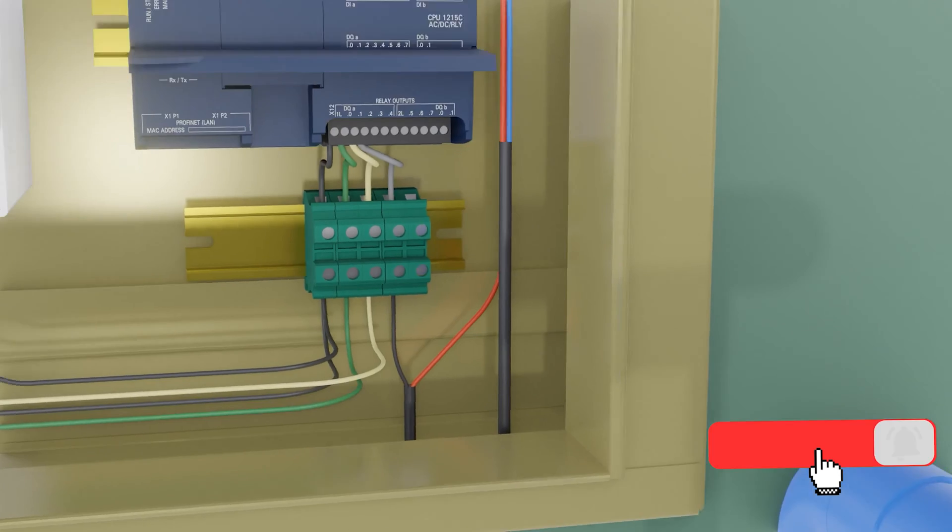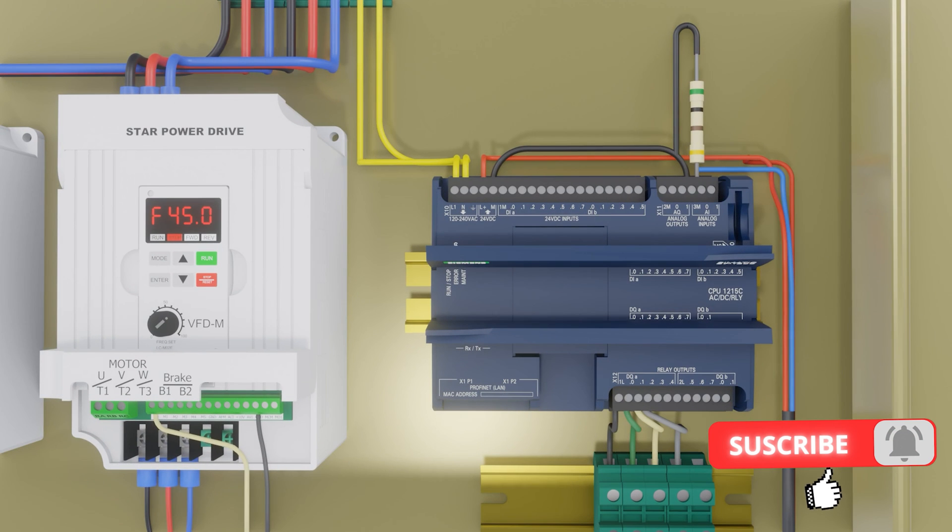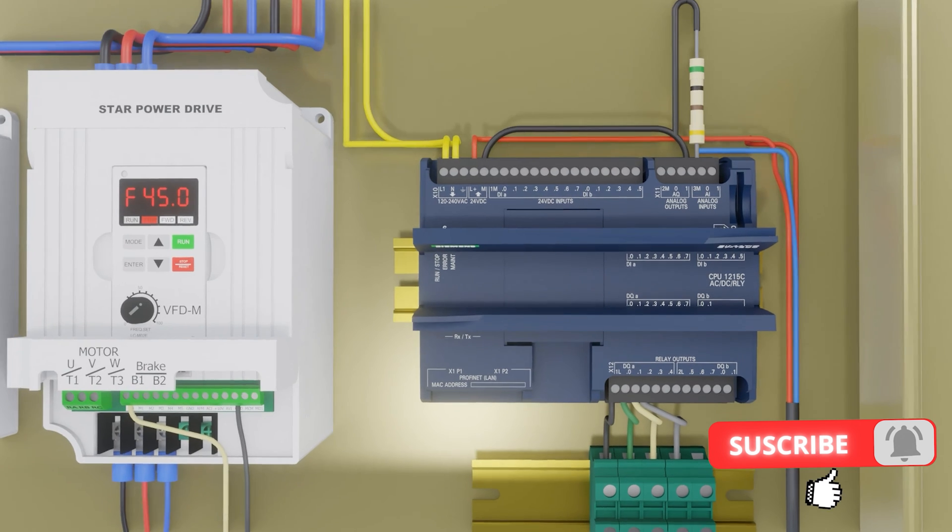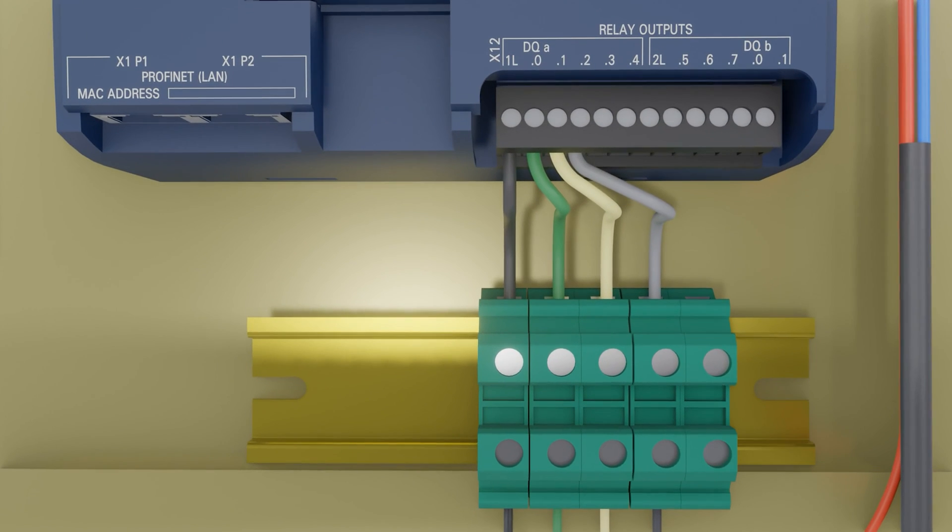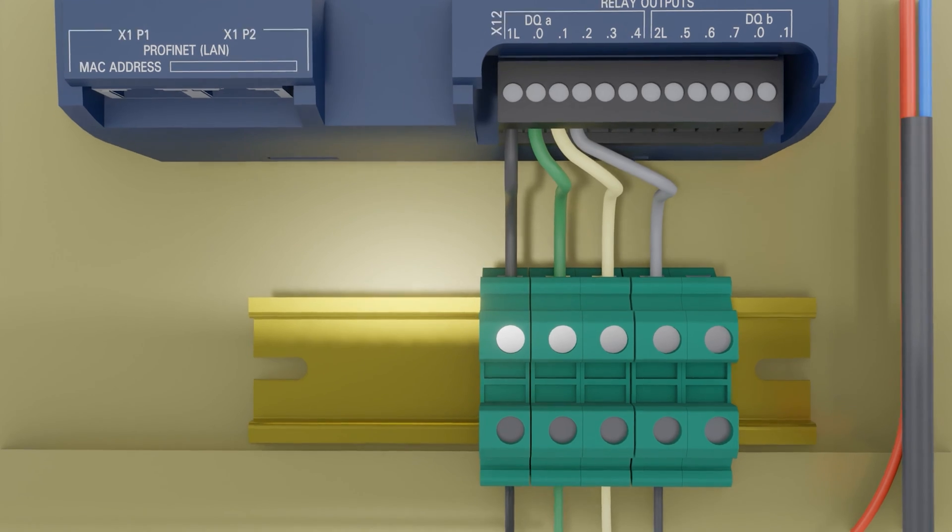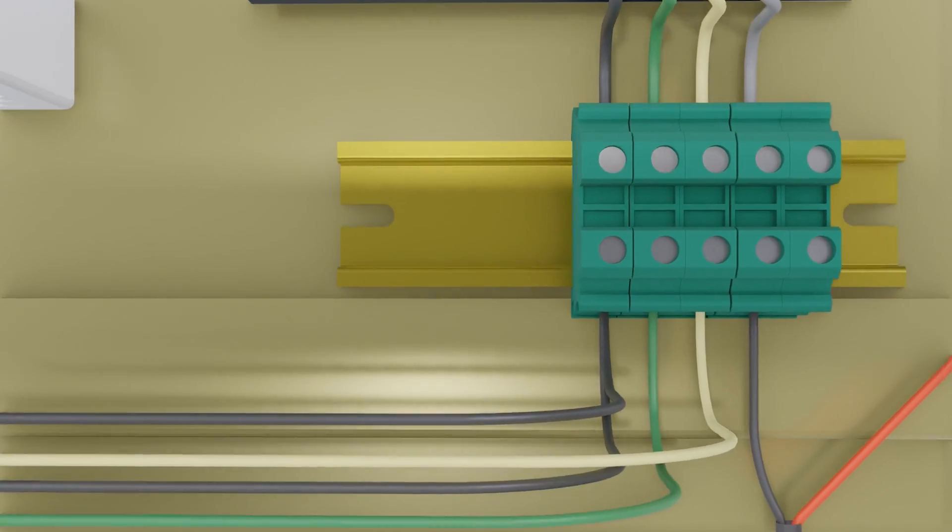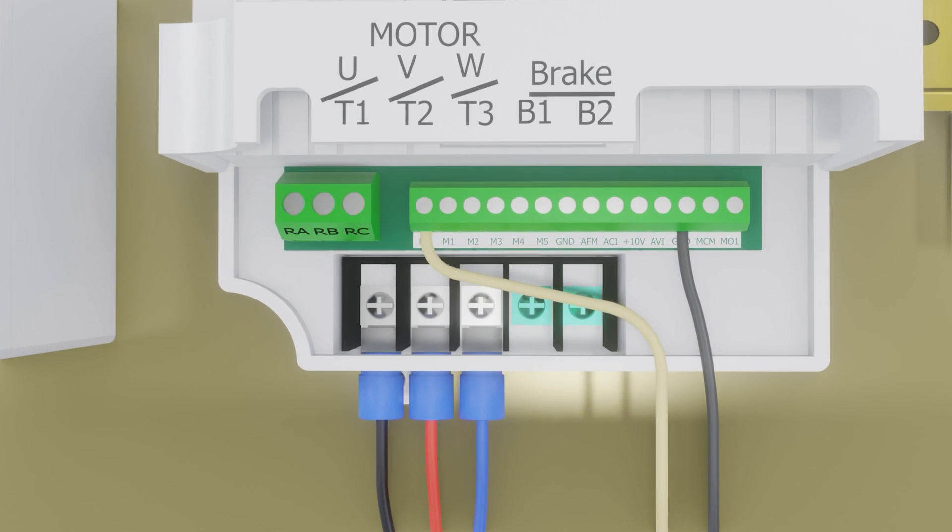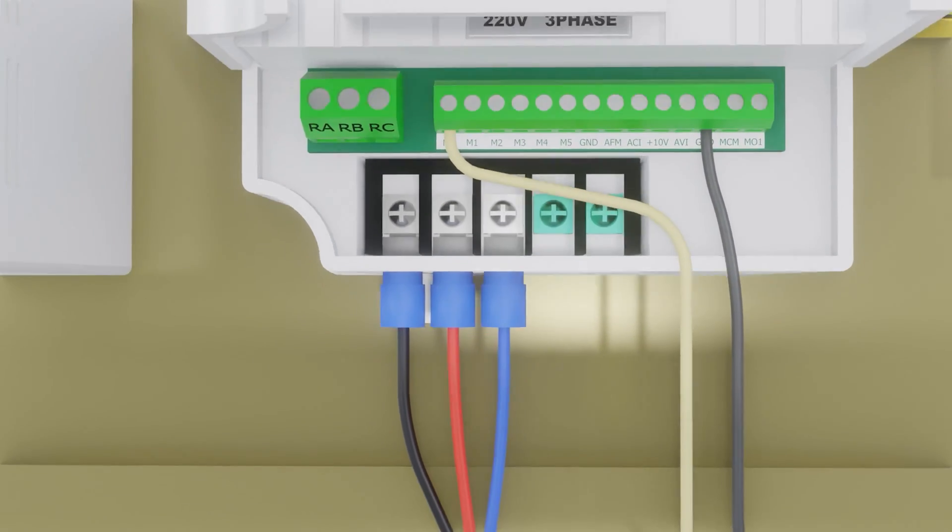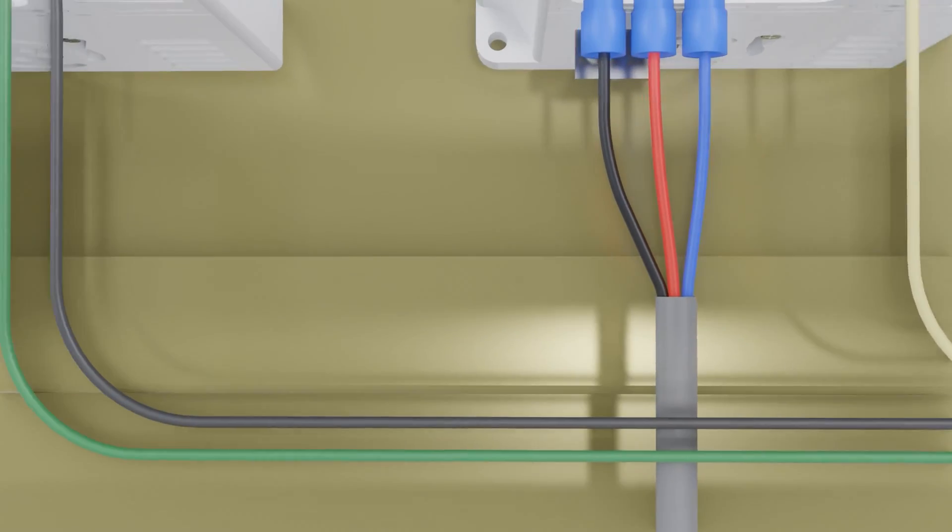We observe the connection of the pressure transmitter. Connected to the PLC, it is a current transmitter, since it uses 2 cables in addition to the resistance. In the PLC, 3 outputs are being used, Q0.0 is frequency drive 1, Q0.1 is frequency drive 2, and Q0.2 is the solenoid valve. Each drive is connected to its digital inputs which allows the water pump to operate.